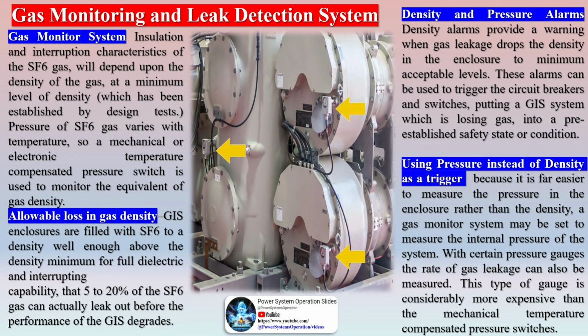Gas monitor system. Insulation and interruption characteristics of the SF6 gas will depend upon the density of the gas, at a minimum level of density which has been established by design tests. Pressure of SF6 gas varies with temperature, so a mechanical or electronic temperature compensated pressure switch is used to monitor the equivalent of gas density.